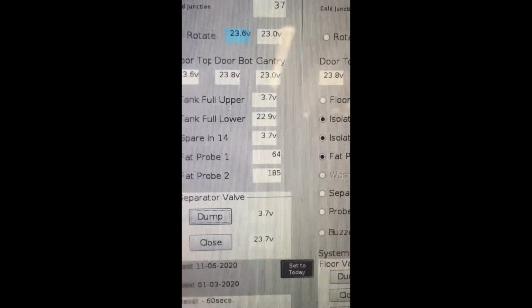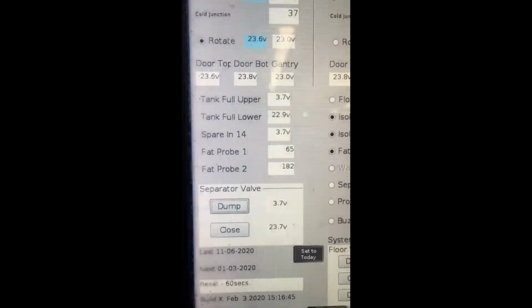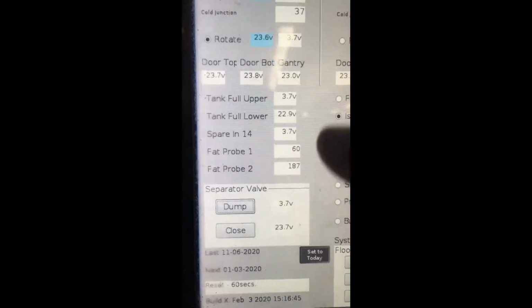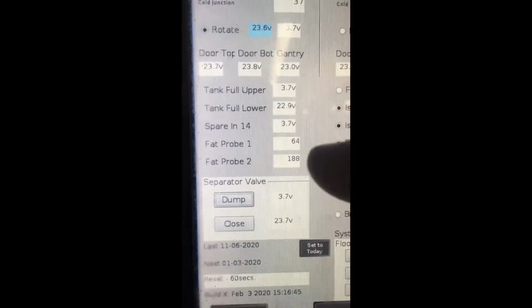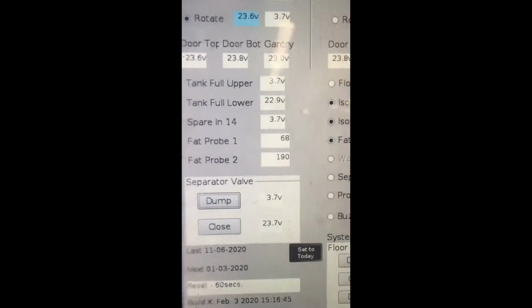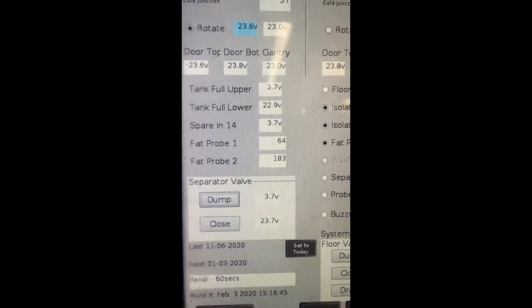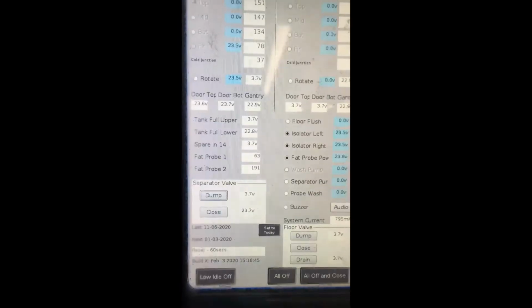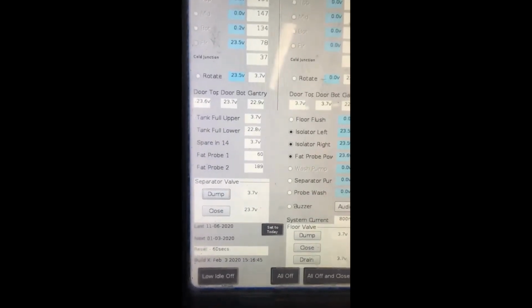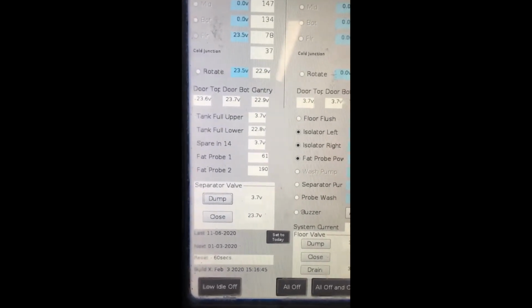We know that the fat separator is full of fluid, so the very bottom of that should be water, and we can see the values here reflect that. These values should be below 600. We will now test the separator valve and drain. To do this, we come to the separator valve section here.